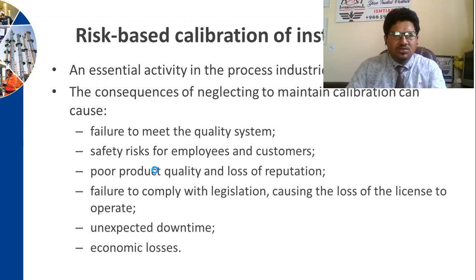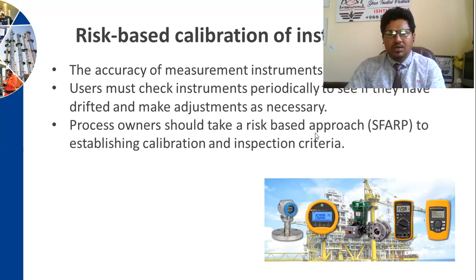Unexpected downtime, economic losses. Now, the accuracy of measurement instruments drifts over time, especially for the process industry. This is one of the important elements, I'm telling you. Make sure all your measuring equipment is well calibrated by a globally acceptable and accredited laboratory, because the accuracy of measurement instruments drifts over time. Users must check instruments periodically to see if they have drifted and make adjustments as necessary. Process owners should take a risk-based approach to establish calibration and inspection criteria.